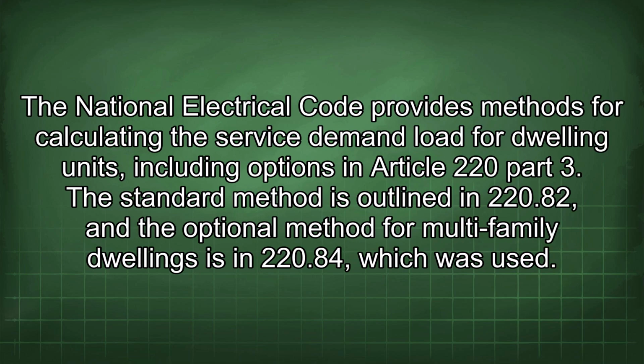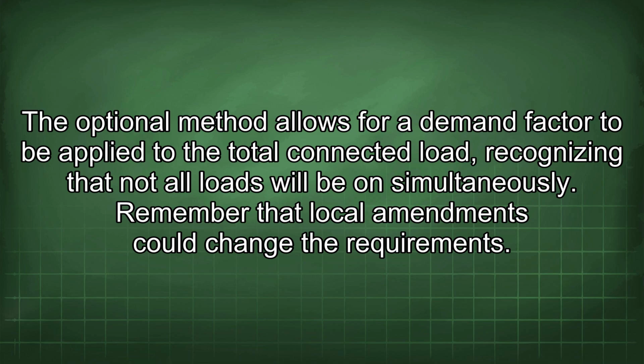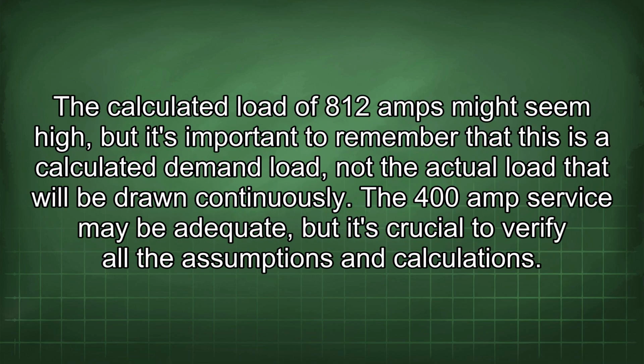The National Electrical Code provides methods for calculating the service demand load for dwelling units, including options in Article 220 Part 3. The standard method is outlined in 220.82, and the optional method for multifamily dwellings is in 220.84, which was used. The optional method allows for a demand factor to be applied to the total connected load, recognizing that not all loads will be on simultaneously. Remember that local amendments could change the requirements. The calculated load of 812 amps might seem high, but it's important to remember that this is a calculated demand load, not the actual load that will be drawn continuously.